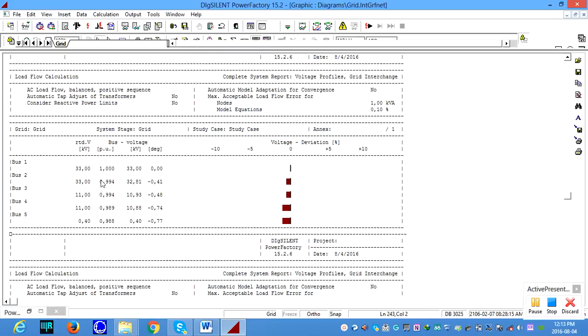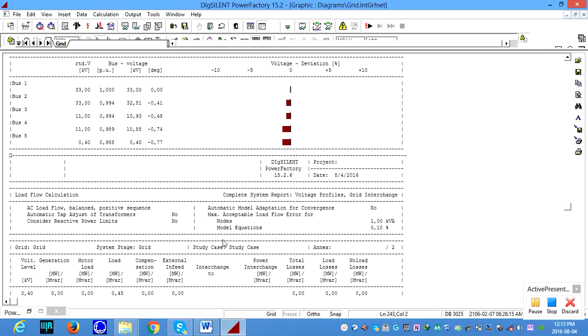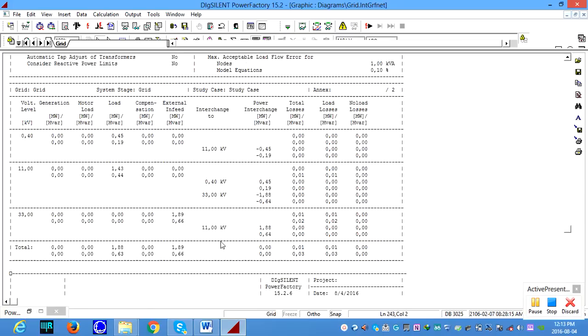So you can see the per unit is maintained as per the standards. The lowest one is 0.989. Okay, and the grid voltage profile, you can see it is less than plus or minus 5% deviation as per the IEEE and IEC standards. And also you can see the grid results.